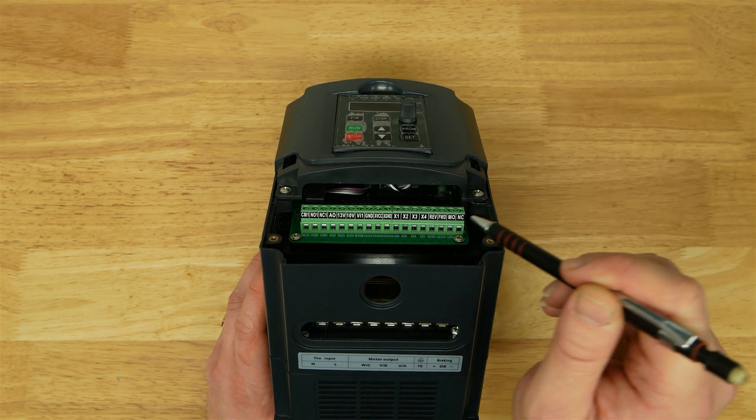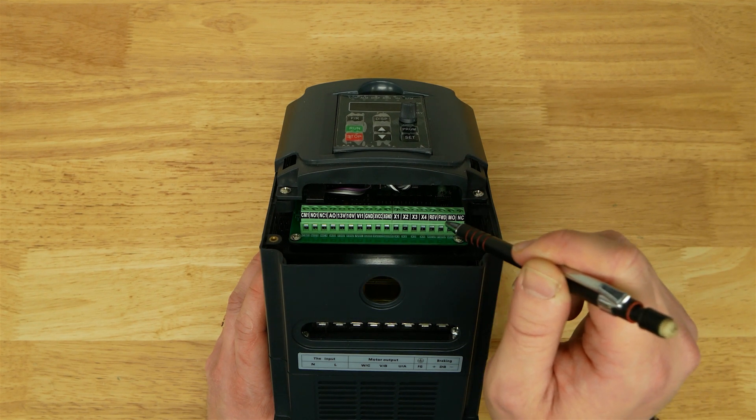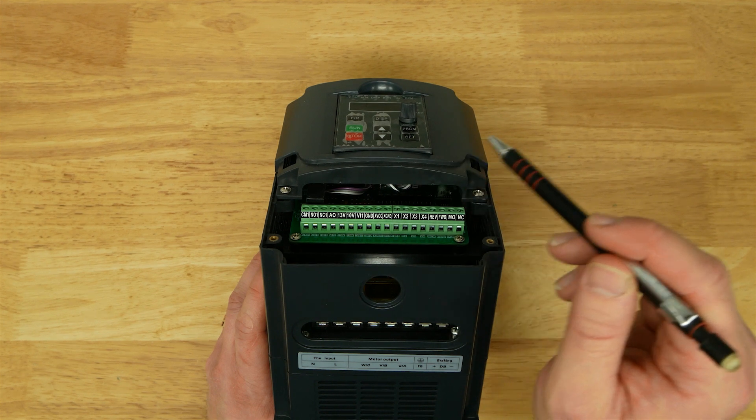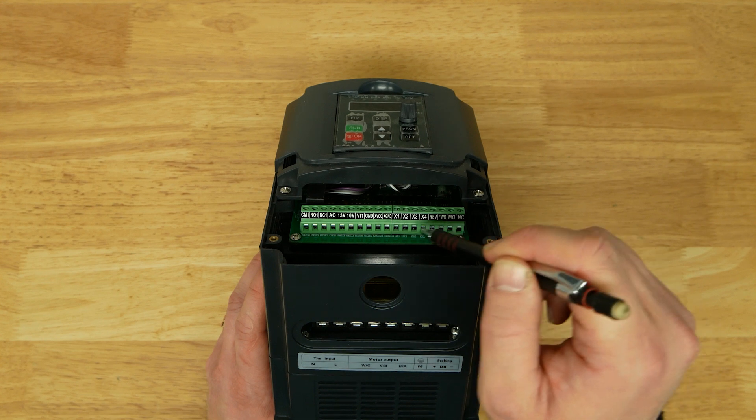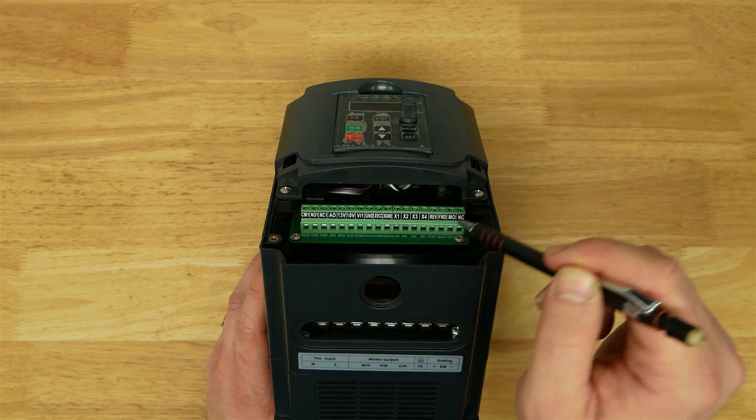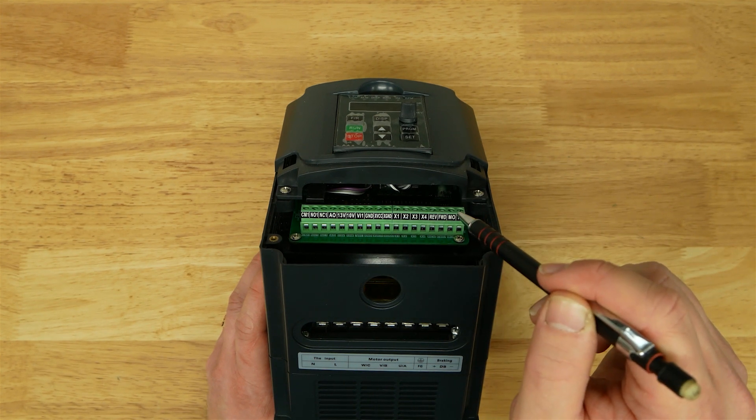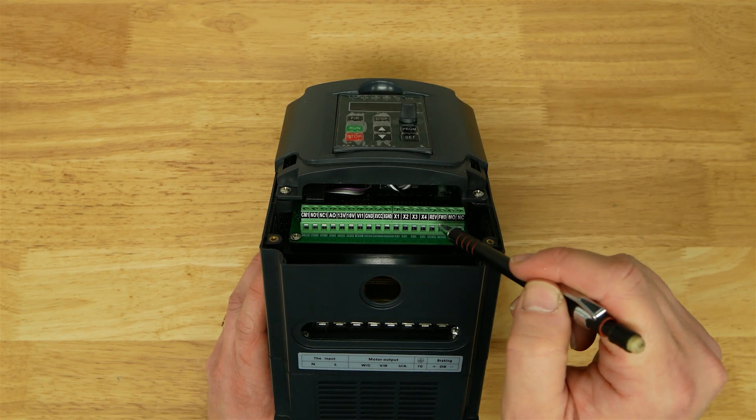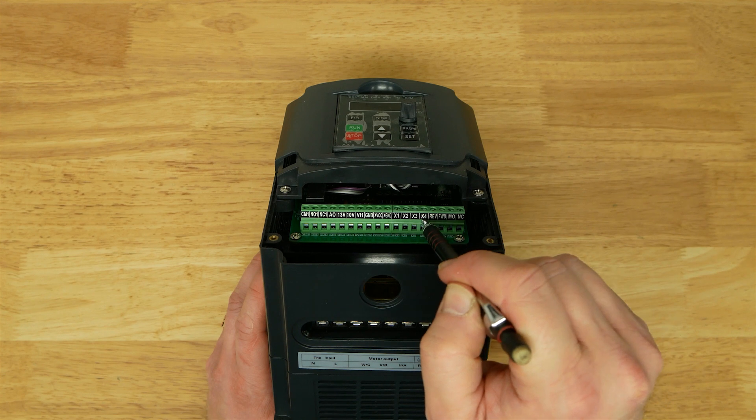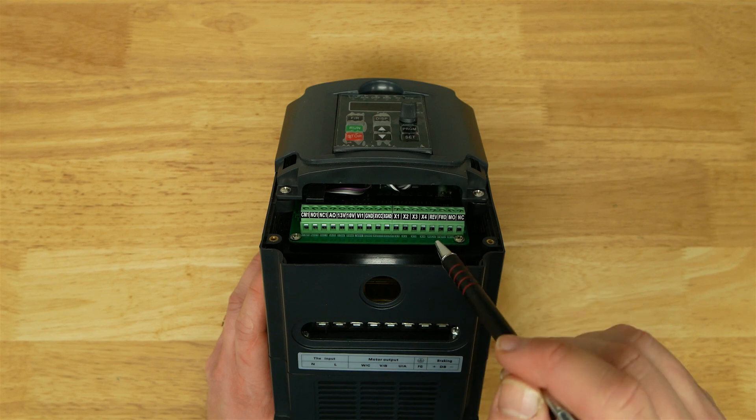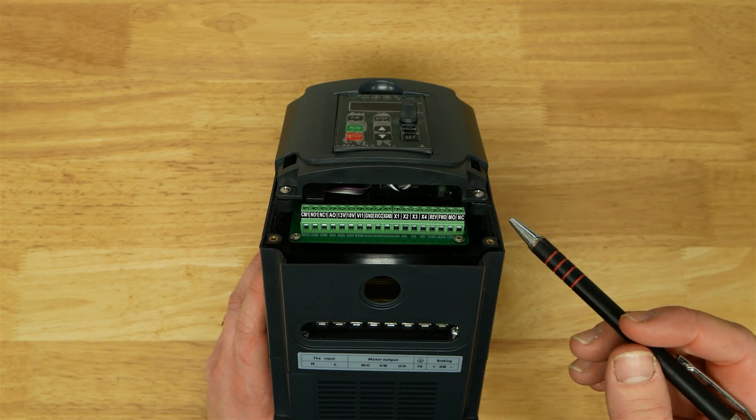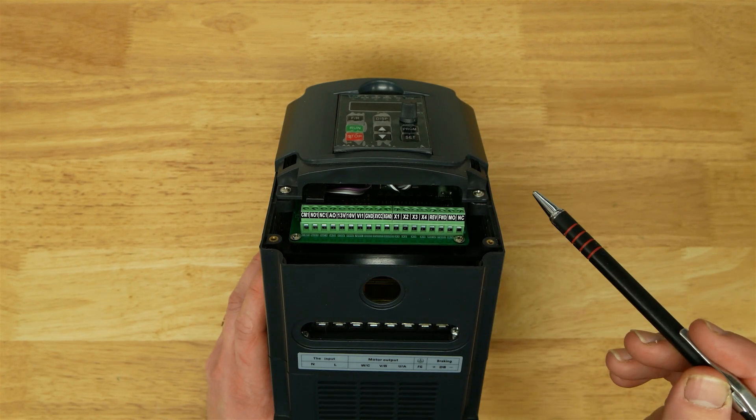For our purposes, we're probably going to use momentary switches. If I remember rightly, the switch goes in, you have forward, switch, ground. When you make a momentary contact, it switches the motor on. Then you can push the brake with one of these, using a normally closed switch. When you want to turn it off, you just break the connection. Since we're using an emergency stop, I prefer that to be normally closed. So when you hit the e-stop, it locks in the open position.